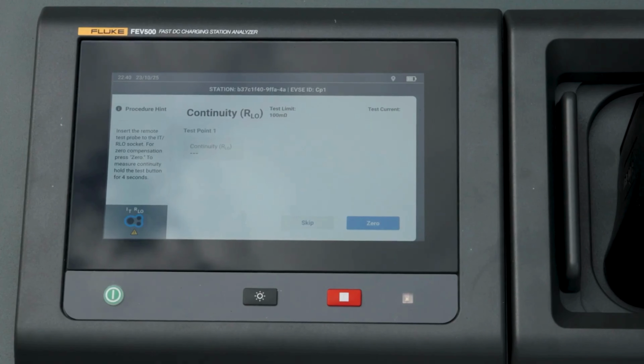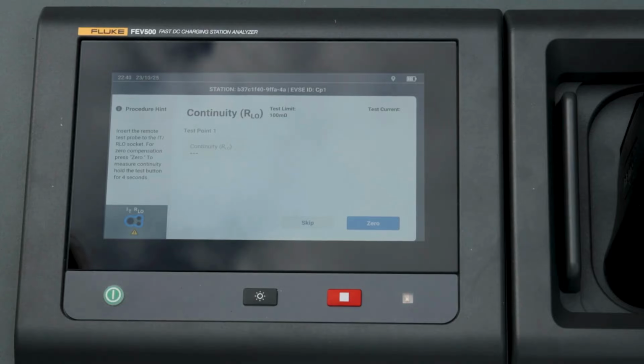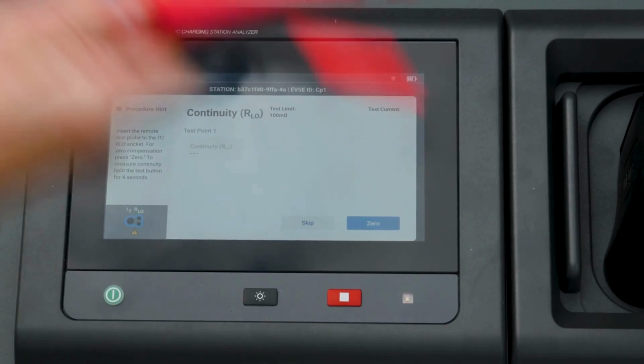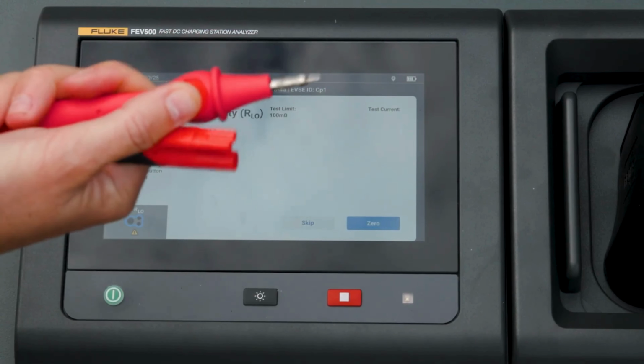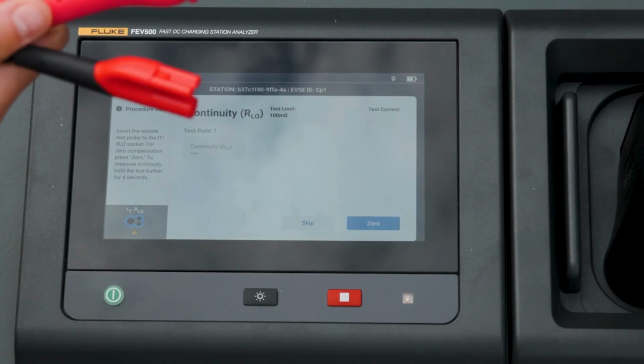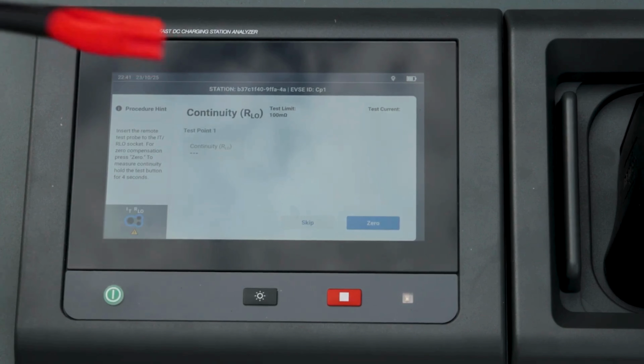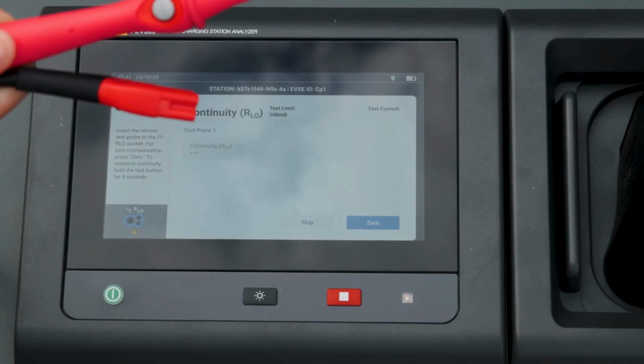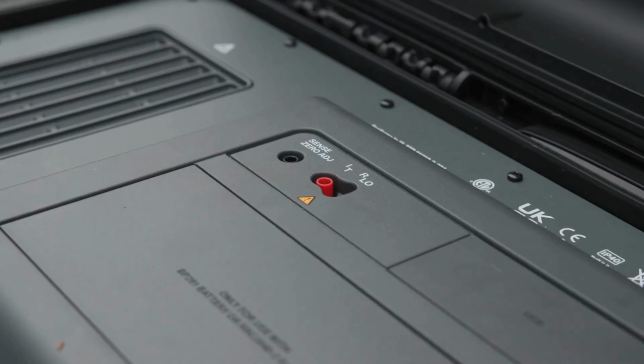Now this brings us to our continuity measurement. This is optional, kind of the last test before we get into the auto test format. You do have the option to skip it, but I'm going to walk through it. The continuity measurement basically uses a test probe or remote test probe that comes with the unit, which has a little test button. We're going to use this to connect to the different metal parts of the housing of the charging station to measure for continuity.